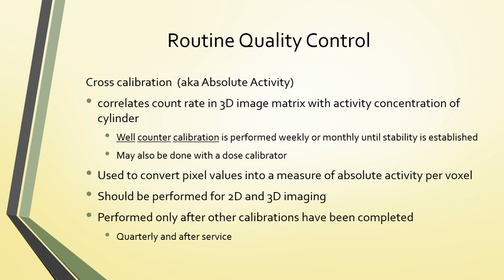Now, cross calibration, also known as absolute activity or the well counter calibration, this correlates the count rate in the 3D image matrix with the activity concentration of the cylinder. The well counter calibration is performed weekly or monthly until stability is established. It may also be done with a dose calibrator. It's used to convert pixel values into a measure of absolute activity per voxel. It should be performed for 2D and 3D imaging, and it's performed only after other calibrations have been completed, and it's done quarterly or after service. And this is also typically performed by a field service engineer.